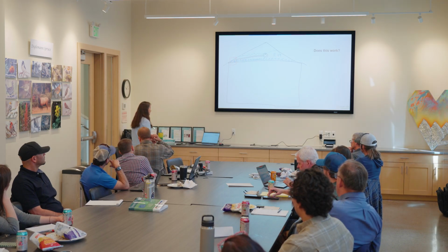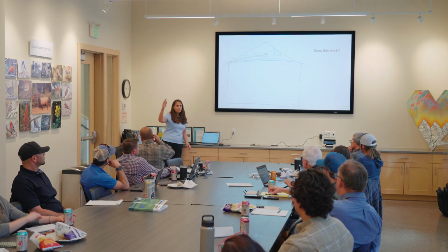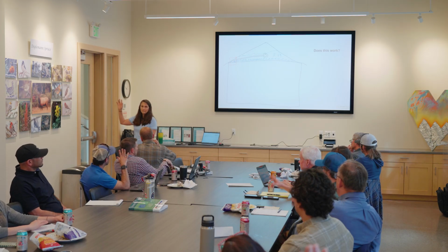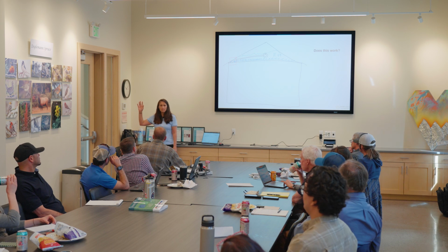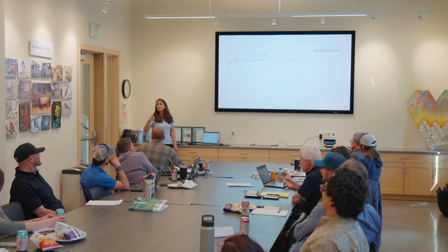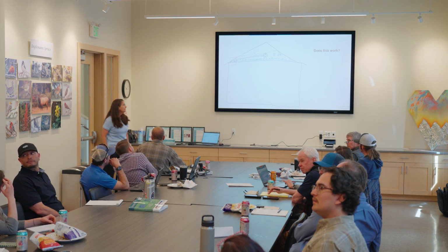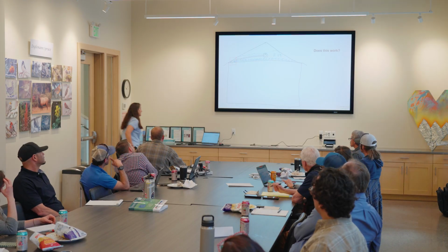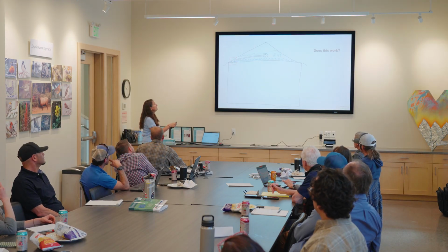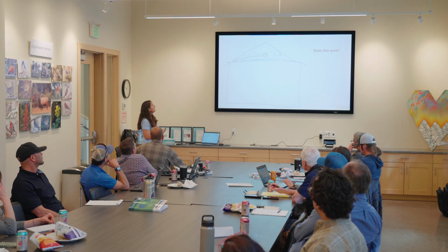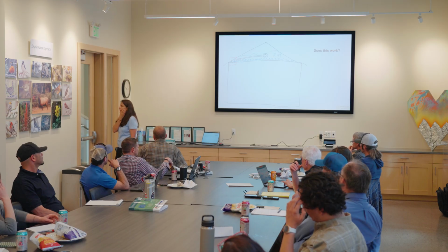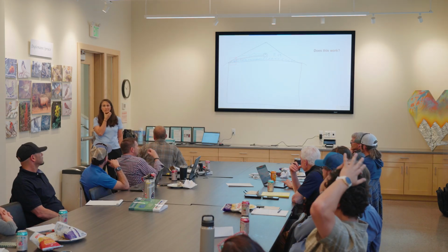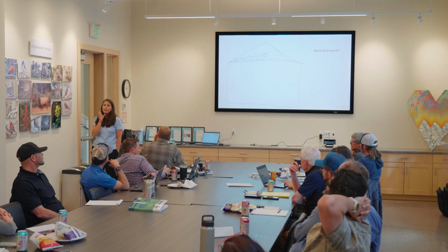So now that I explained this, how many of you now say that this works? All right. How many of you still say this doesn't work? All right, Derek, what do you say? Where's his R value above that ductwork? This here? Above it? Yep. No, where that transition is, where it drops through the ceiling. Right here? Yeah.